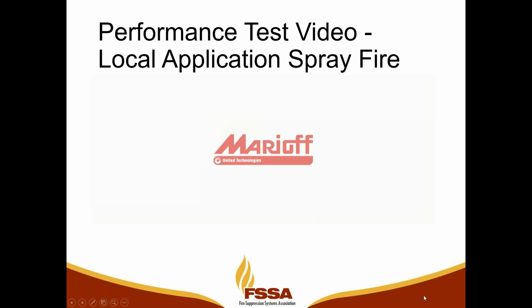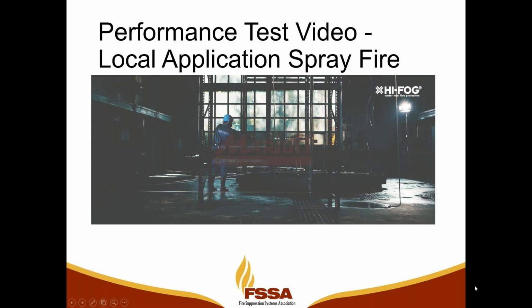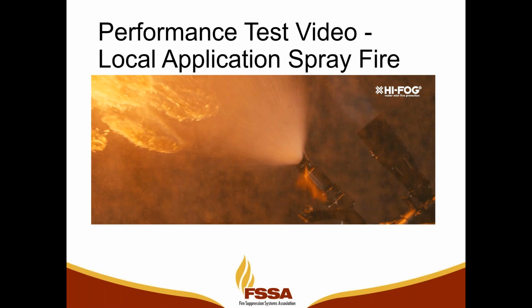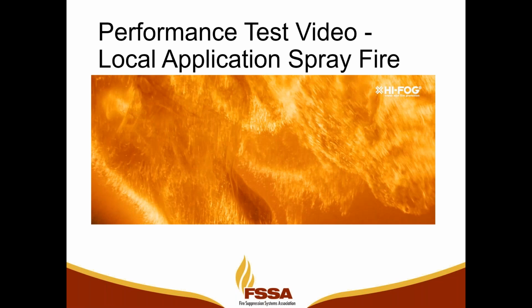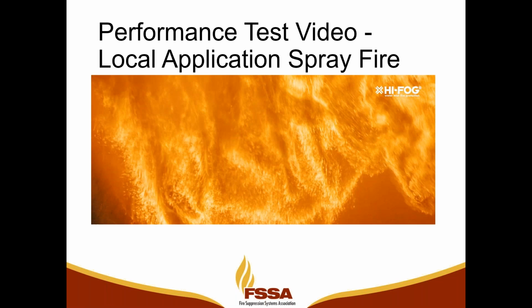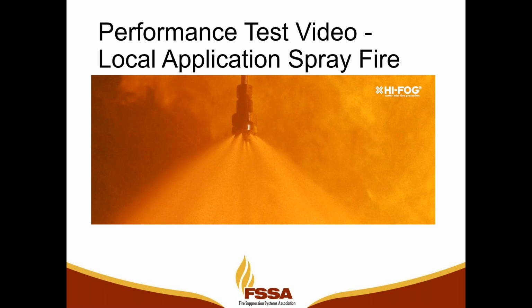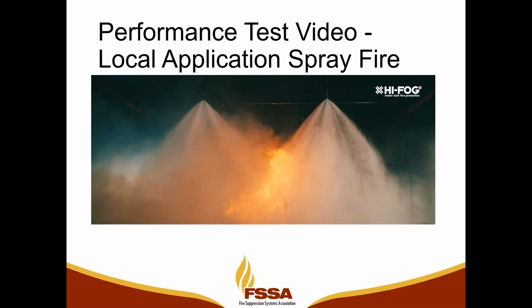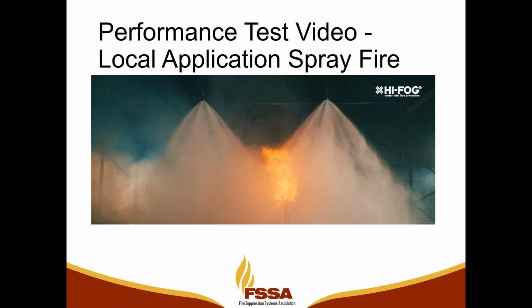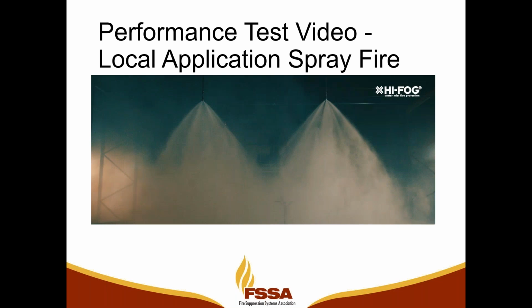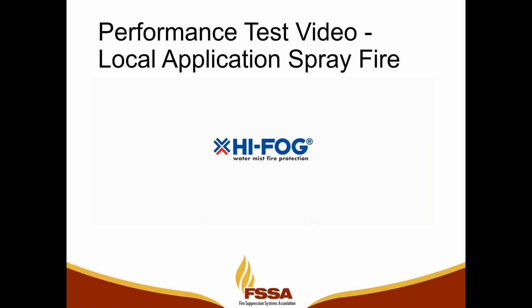So this is another application, for local application spray fires. Sometimes you'll have hydraulic hoses in industrial areas or on machinery, gas turbines, those types of things, that may break and then ignite into a spray fire. So with water mist type systems, we also have to be able to protect those types of environments. But again, as a performance-based test, in order to get the listing, you have to show that you can actually extinguish it. Now, one thing to note on that video, the fuel was actually still being discharged from the spray head as the water mist system was extinguishing the fire and put it out. Next slide.